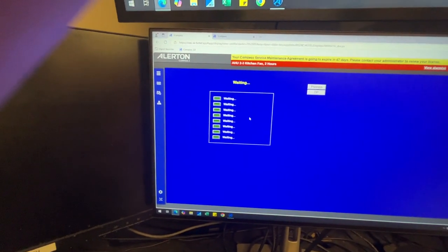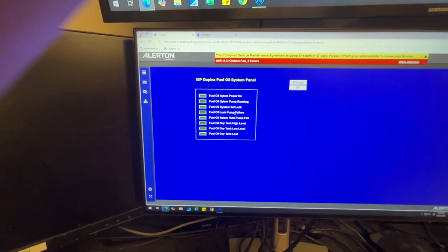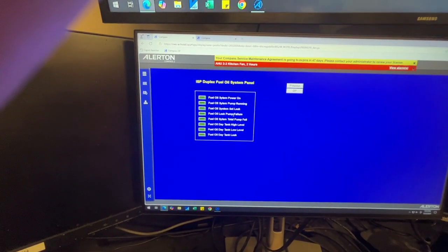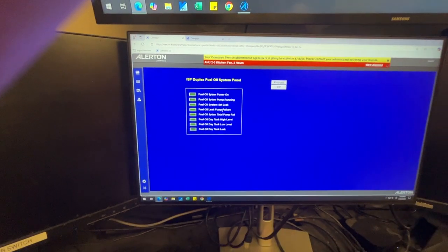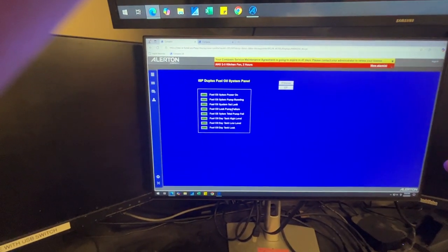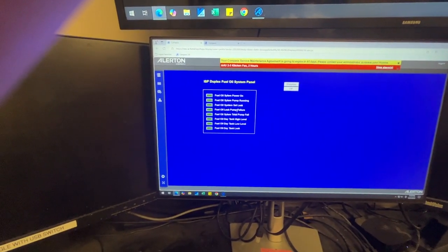Fuel monitoring system. So the fuel tank in the basement is for the generator, and there's floats actually on the 3rd floor roof. There's a storage tank of like 500 gallons. As the fuel level goes down, it will command the system downstairs to pump fuel up to the roof.